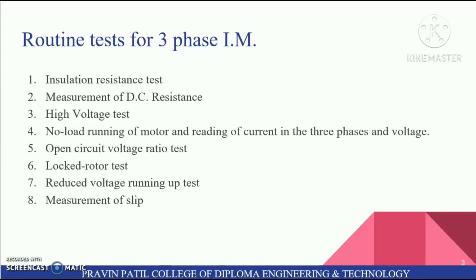So routine tests for 3-phase induction motor are: first one is insulation resistance test, second measurement of DC resistance, high voltage test, no load running of motor and reading of current in 3 phases and voltage, open circuit voltage ratio test, locked rotor test, reduced voltage running up test, and measurement of slip.